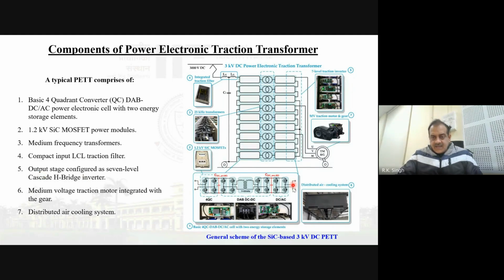This entire architecture describes the solid state transformer or power electronic traction transformer. Nowadays this has almost taken over the fundamental line frequency transformer, because the size gets reduced significantly, almost 1,000 times, since the distribution transformer used to be huge, with a CRGO core that is big and bulky.